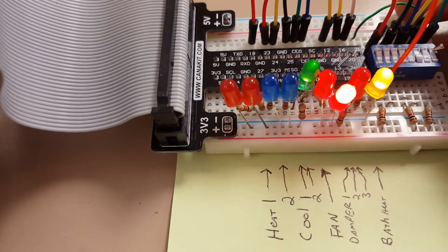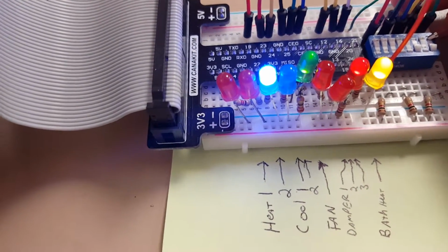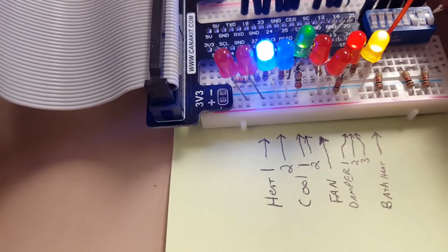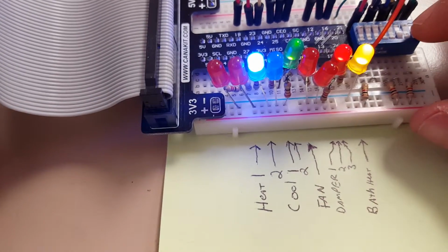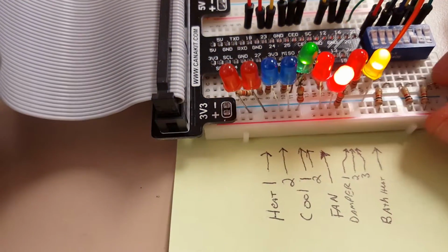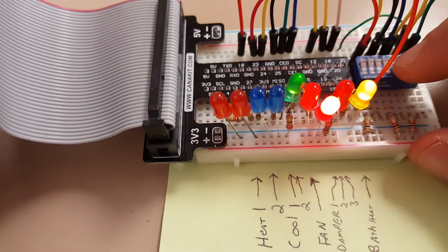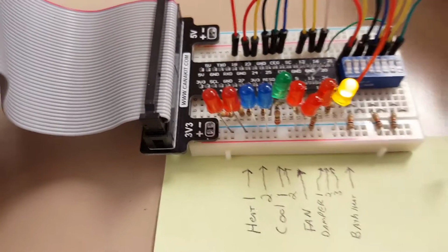If there's a call for cooling, let's say here, that's going to shut off that zone damper and open the one that needs cooling. That way, an area that wants ventilation is only going to get ventilation and not heating or cooling. So it tries to be a little bit intelligent with it.